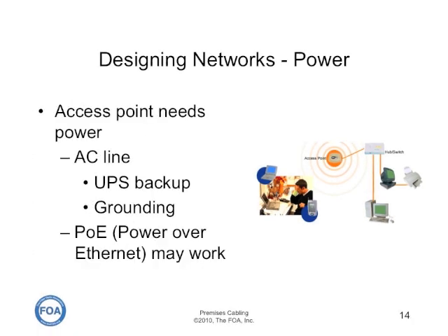Access points also require power. If it's AC powered, it will need an uninterruptible power backup and data quality grounding. If it's using power over ethernet, the access point must be within the limits of the power able to be delivered over the unshielded twisted pair cabling using power over ethernet.